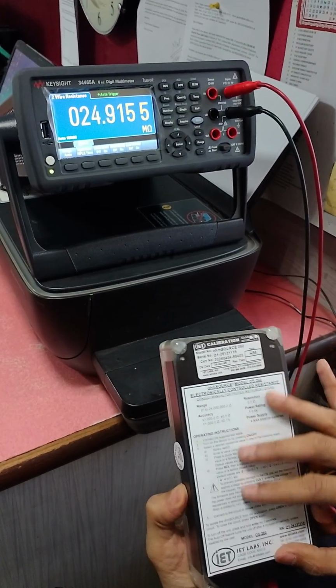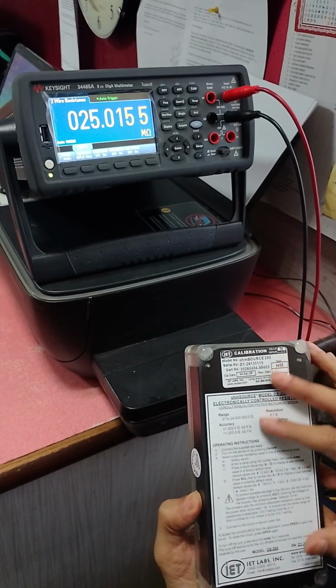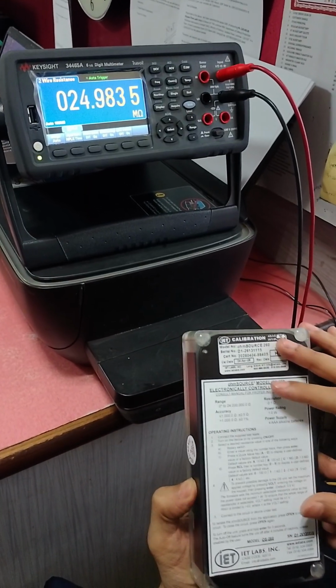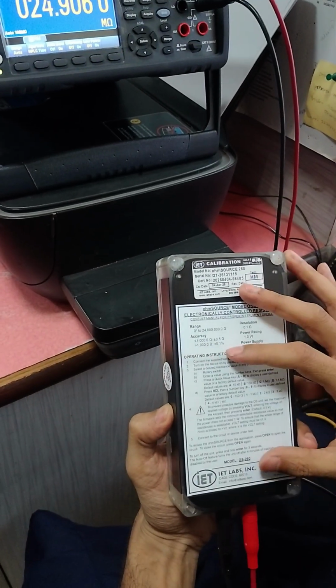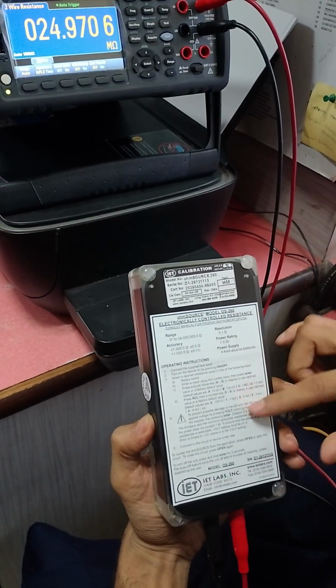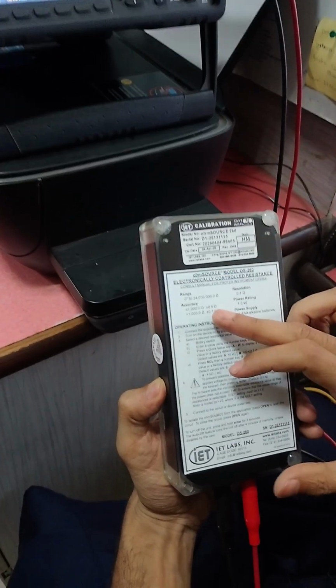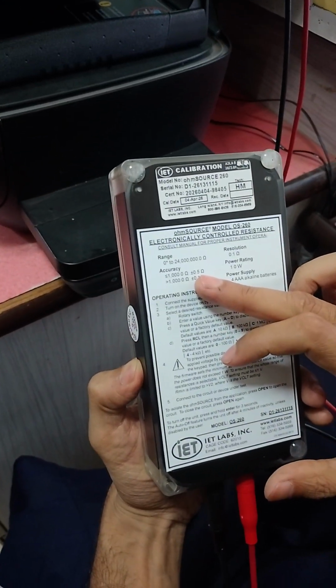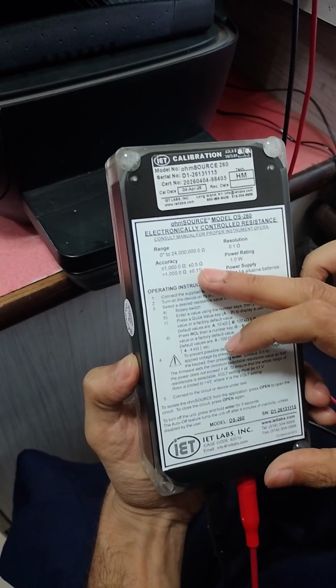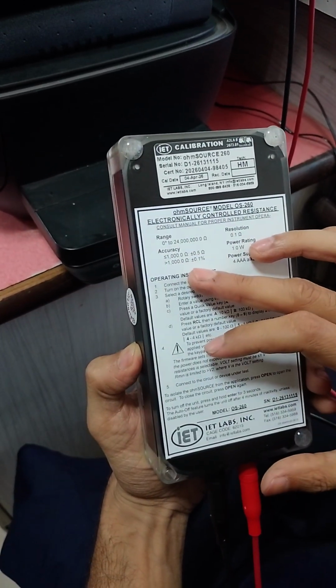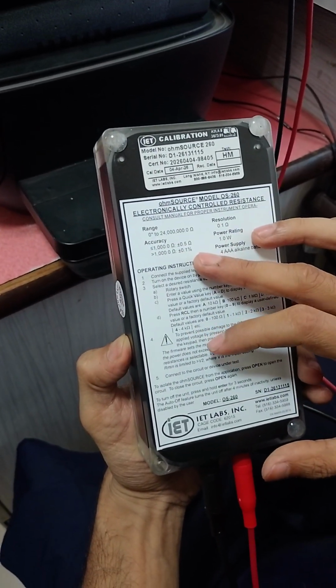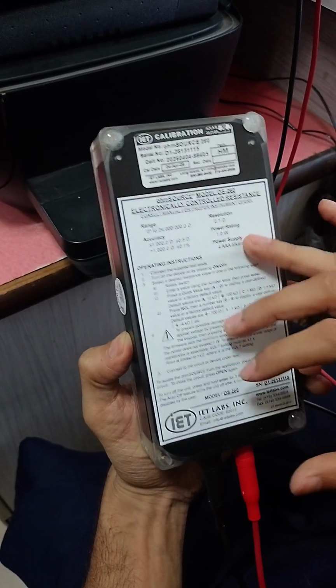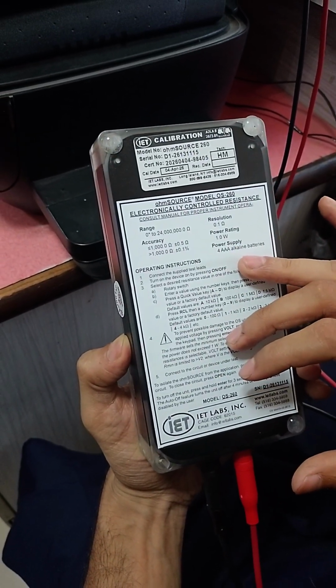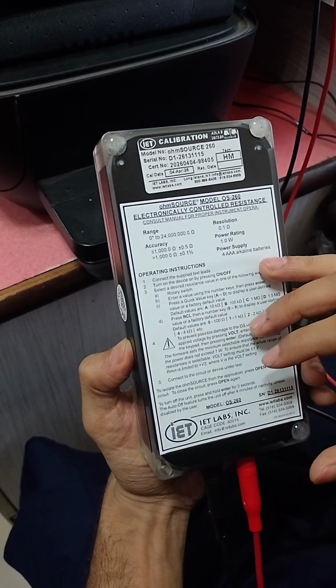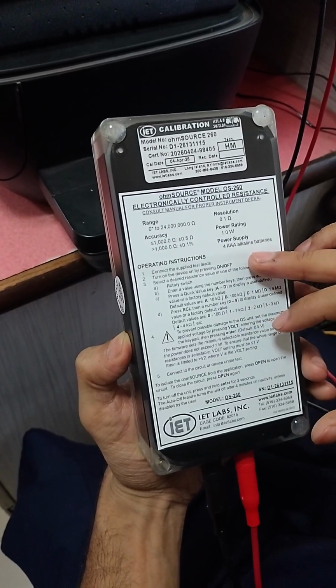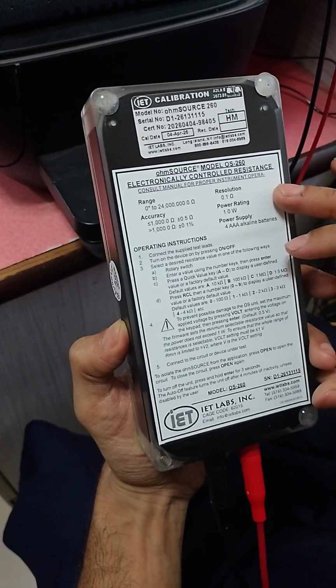On the back side, this unit comes with all the details like model number, serial number, calibration certificate, and all the specifications, like for below 1000 ohms it has accuracy of plus minus 0.5 ohm, and above 1000 ohms it has accuracy of 0.1%. This is basically sourced by 4 AAA alkaline batteries, which you require in order to operate this unit.